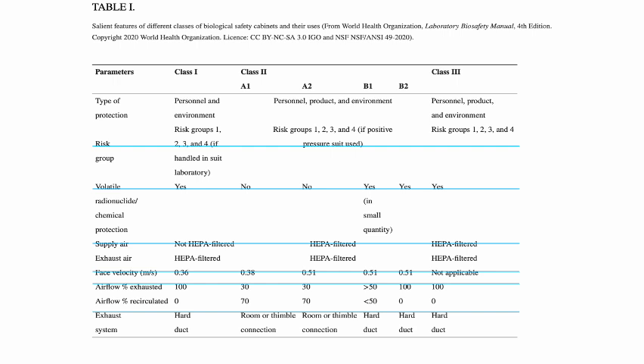Now in a Class 3 biosafety cabinet, you can work with risk groups 1, 2, 3, and 4, so it is complete. In terms of chemical protection and protection from toxic substances, including toxic vapors, Class 2A1 and 2A2 cannot provide proper protection against chemicals and toxic vapors, because of their exhaust system. The exhaust system of Class 2A1 and Class 2A2 is room exhaust. That means toxic substances would be exhausted into the room itself, which is hazardous to the worker. That's why Class 2A1 and A2 cannot provide chemical protection and protection against toxic volatile substances.